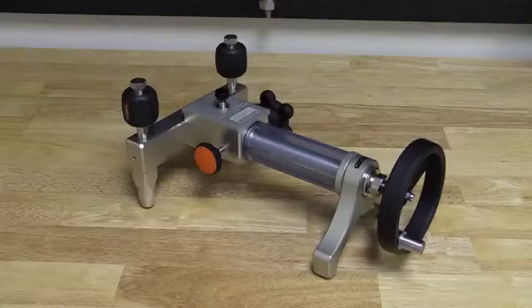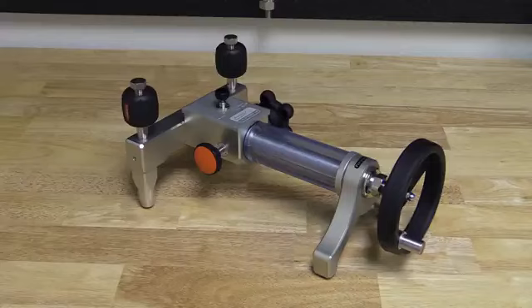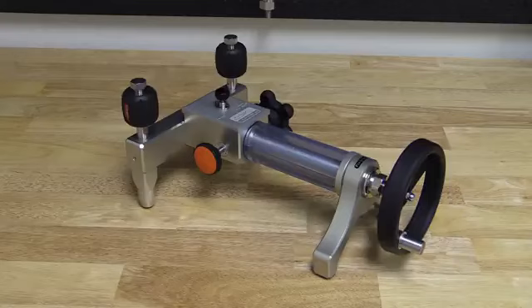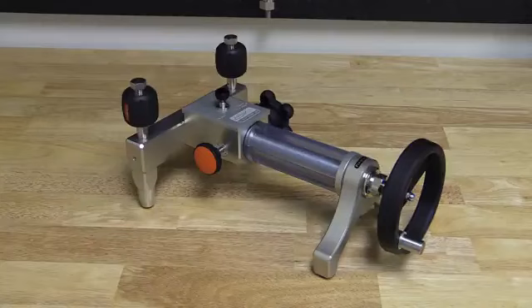To produce stable and high pressure measurements using a hydraulic calibration pump, the gas within the calibration system needs to be removed. Hydraulic test pumps use various types of fluid to generate high pressures. Because gas is more compressible than liquid, purging most if not all the gas out of the system will allow for maximum pressures to be generated and the best stability to be realized.